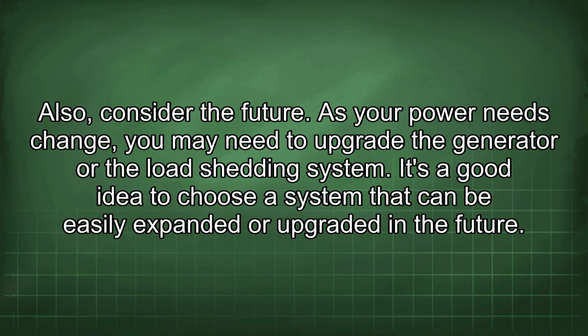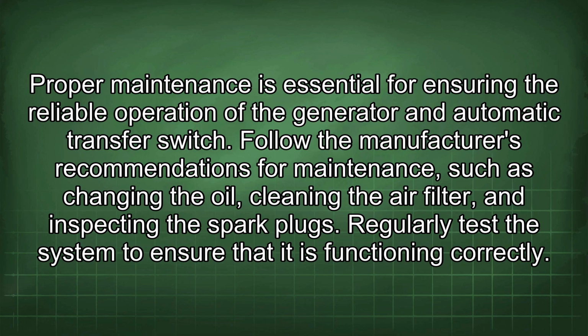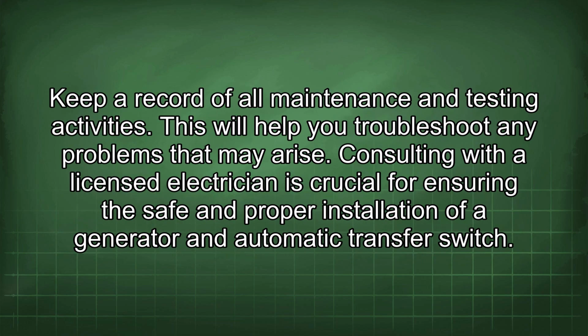Also, consider the future. As your power needs change, you may need to upgrade the generator or the load shedding system. It's a good idea to choose a system that can be easily expanded or upgraded in the future. Proper maintenance is essential for ensuring the reliable operation of the generator and automatic transfer switch. Follow the manufacturer's recommendations for maintenance, such as changing the oil, cleaning the air filter, and inspecting the spark plugs. Regularly test the system to ensure that it is functioning correctly. Keep a record of all maintenance and testing activities. This will help you troubleshoot any problems that may arise.